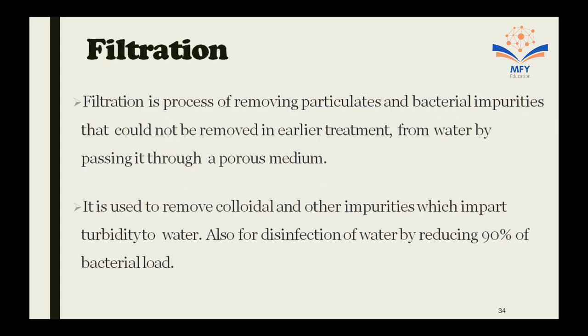Last one will be filtration. Filtration is the process of removing particles and bacterial impurities that could not be removed in earlier treatment from water by passing it through a porous medium. It is used to remove colloidal and other impurities which impart turbidity to water, and also for disinfection of water by reducing 90% of bacterial load. It is also used to reduce odor and color by arresting them in filter media.